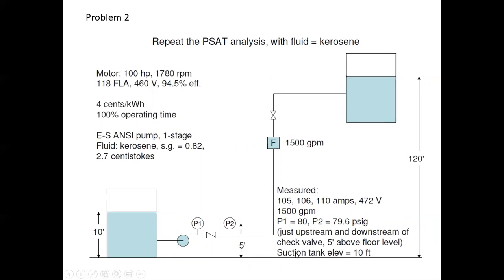Now life gets a little more interesting here. This is where I really need to rewrite some of this, because it gets a little bit confusing at this point. So we're going to change the fluid. Everything's going to stay the same except the fluid, but some of these measured quantities would change, and that's what I need to be a little clearer on. So you repeat the analysis in terms of the elevation, the pipe size, and the check valve, but the pressures we're going to see are going to change. The flow rate we're going to keep the same. The elevation and all that stuff are going to be the same.